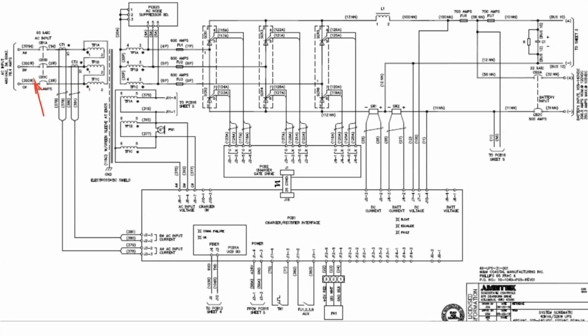And then we have our delta primary. This is the isolation transformer that I talked about earlier on in the presentation. And you can see there is absolutely no electrical connection between the primary and the secondary. Okay, the secondary is a separately derived source. There is no electrical connection whatsoever. So there is no way anything can feed back this way, DC wise, through that transformer. It's absolutely impossible. Okay. This transformer does step the voltage down to about 120 volts phase to phase for a 60 cell system.